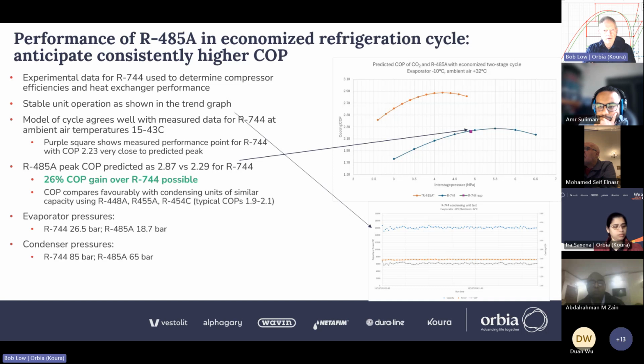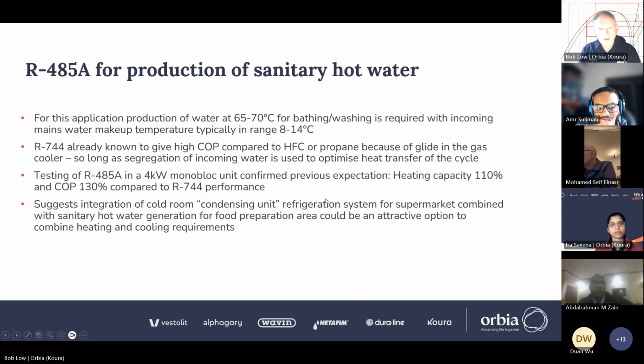The points to note again, the evaporator pressures are lower with the blend, 19 bar compared to 27 bar, and the condenser pressure, 65 bar, again a true condensing pressure compared to 85 bar for CO2.